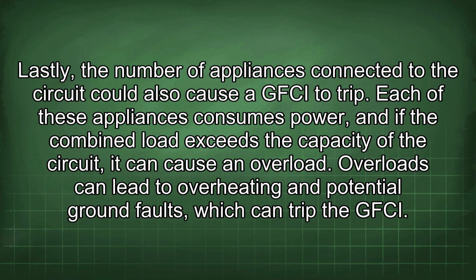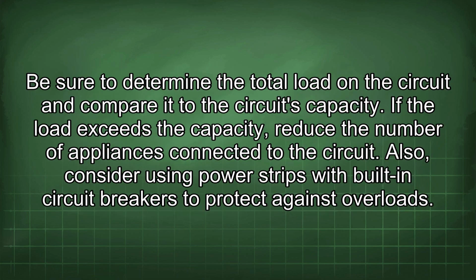Lastly, the number of appliances connected to the circuit could also cause a GFCI to trip. Each of these appliances consumes power, and if the combined load exceeds the capacity of the circuit, it can cause an overload. Overloads can lead to overheating and potential ground faults, which can trip the GFCI. Be sure to determine the total load in the circuit and compare it to the circuit's capacity. If the load exceeds the capacity, reduce the number of appliances connected to the circuit. Also, consider using power strips with built-in circuit breakers to protect against overloads.